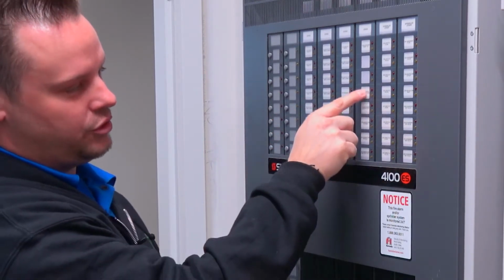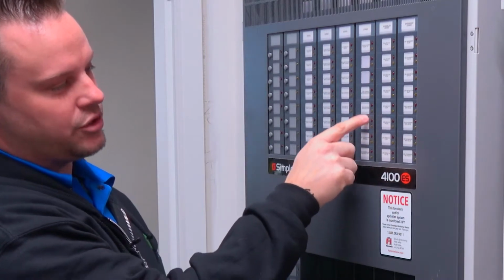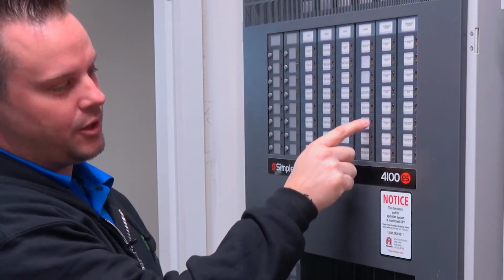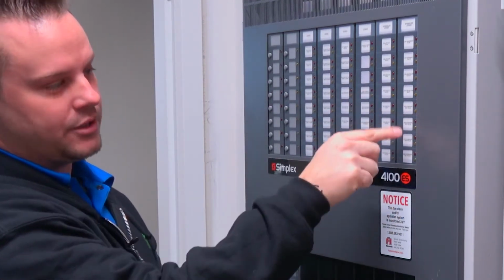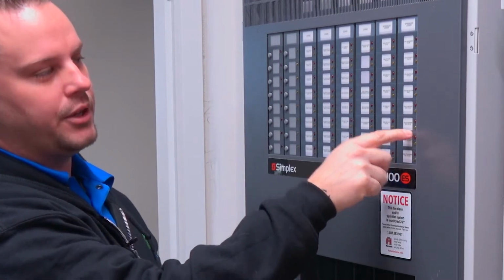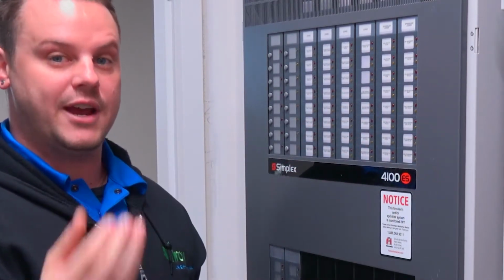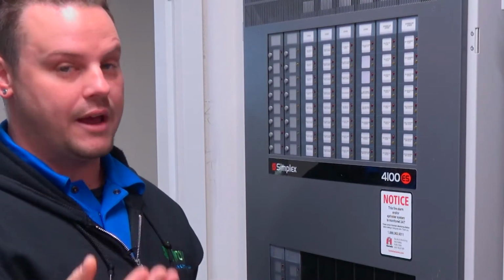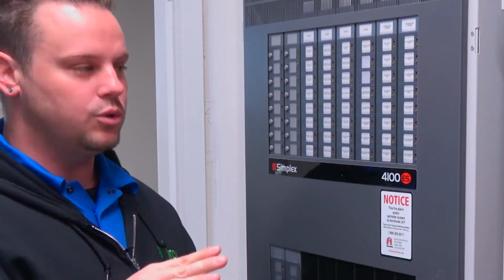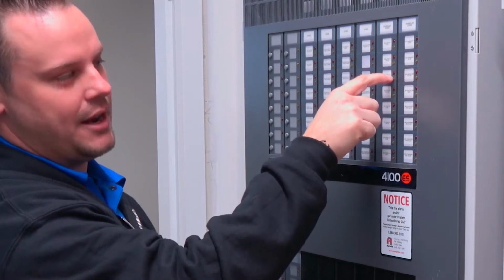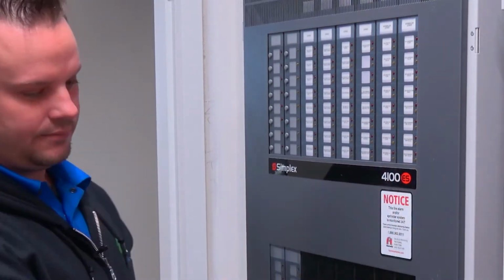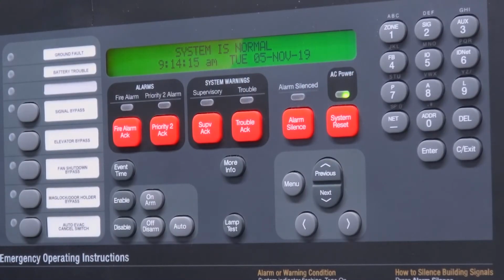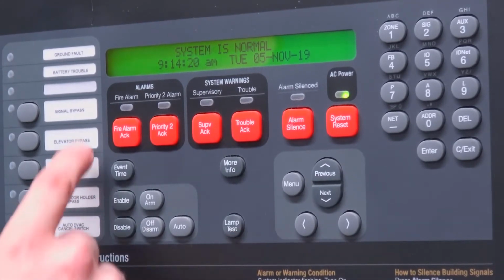Also, you have your generator stuff here on this side, which are all supervisories. So any supervisory is going to be lighting up your amber LED. Any sprinkler valves or sprinkler low pressures are going to be lighting up amber LEDs. But your sprinkler flows, so if a sprinkler head went off in a unit or wherever, there's going to be flow of water. It hits a flow switch, which then activates a red LED of that floor or whatever zone it's activating in. If you ever had any maintenance, welding, or HVAC work done in the building, what you could do is you could put your bypasses on.